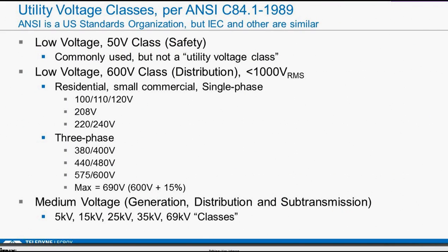You might have heard about voltage classes, like a utility class. So in the U.S., we have a group called ANSI. Usually all their standards are shared with IEEE. Then there's IEC and other similar organizations around the world. These are utility voltage classes per ANSI C84.1-1989. Now, this low voltage class is not an ANSI class, but it's commonly referred to as a safety class. Basically, anything under 50 volts you can touch, you're probably not going to be injured. So it's commonly referred to as kind of a safety class, but it's not a utility voltage class.